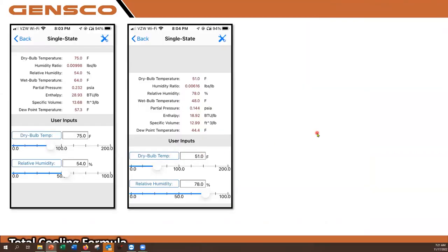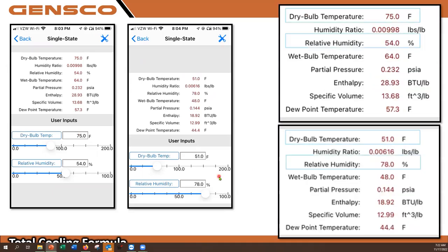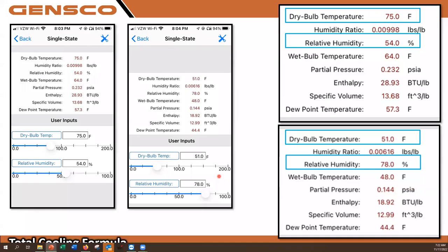If I'm using the app, I can enter dry bulb temperature and relative humidity. It will tell me quite a bit about what's in that air. And my exit air, my supply air, dry bulb and relative humidity. Again, everything I need to know about that air. So there are the actual readings that I just measured on that MSZ GL12.